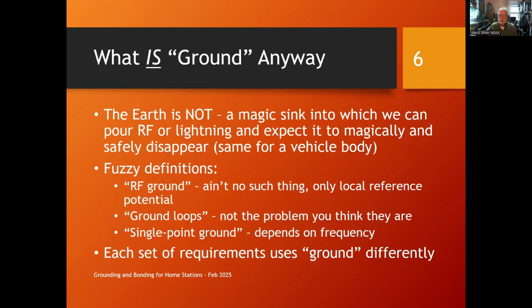Also, there's a couple of myths about the ground. The earth, meaning your backyard or wherever you are, is not some kind of magic 0 volt infinite sink that you pound in a ground rod and you connect whatever you connected to it, and suddenly all the current in that connection just magically disappears. And it's always 0 volts, and you never have to worry about it. And the earth is not like that. It's made out of dirt and rock, and it has resistance, and the resistance varies with where you are in the earth or on the earth or under the earth. And so current flowing through that material causes voltage drops. So you will have all kinds of different voltage potentials around a plot of ground. And so you can't just pour RF or lightning into it and magically expect it to disappear.